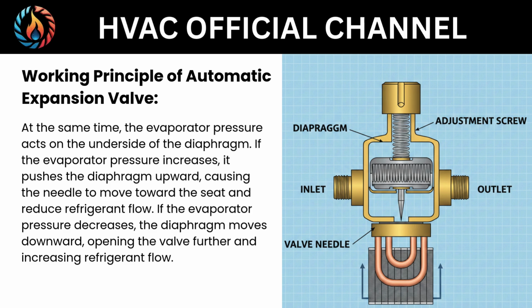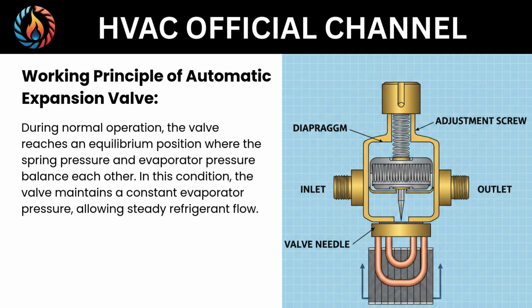If the evaporator pressure increases, it pushes the diaphragm upward, causing the needle to move toward the seat and reduce refrigerant flow. If the evaporator pressure decreases, the diaphragm moves downward, opening the valve further and increasing refrigerant flow. During normal operation, the valve reaches an equilibrium position where the spring pressure and evaporator pressure balance each other. In this condition, the valve maintains a constant evaporator pressure, allowing steady refrigerant flow.